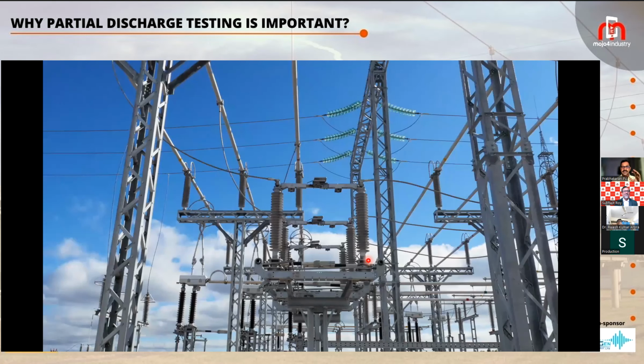This is the acoustic imager, a brief introduction. It is a kind of camera with 64 acoustic sensors and a visual sensor, giving you a wide viewpoint, and it can capture the entire sound or acoustic signal coming from 2 to 100 kilohertz range. Why 2 to 100 kilohertz? That's the question I was trying to answer earlier itself. Most partial discharge sound waveforms or acoustic waveforms are well within that 100 kilohertz range, so this sensor covers the entire range of partial discharge acoustic waveforms.